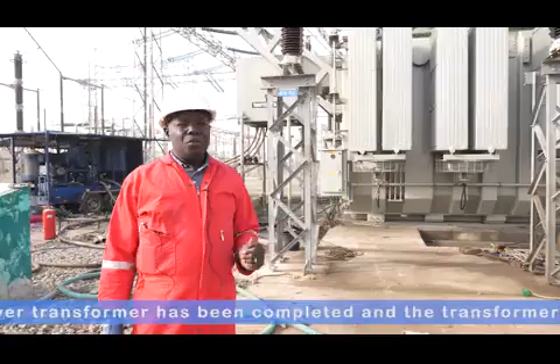So now that T3A is out and T1A is out — and all of them are 150 MVA of the same make — we said, why can't we cannibalize one to make a working unit out of the two? That's what we did. We opened the transformers, removed the bad part from T1A, and replaced it with the good part from T3A.